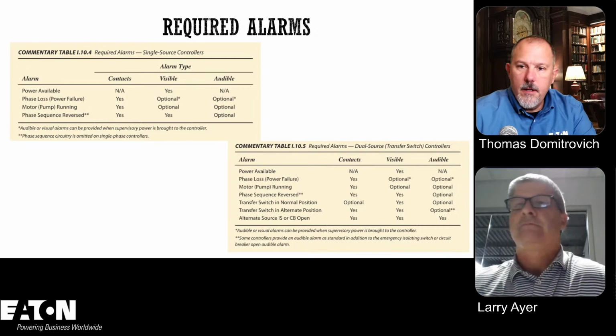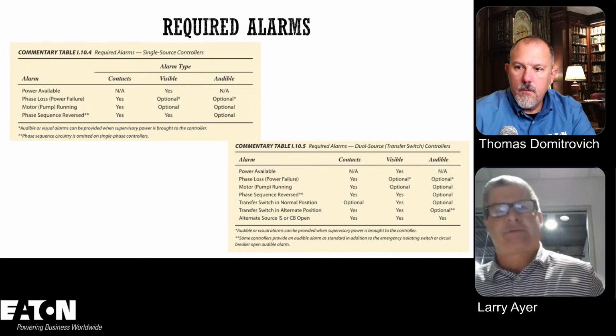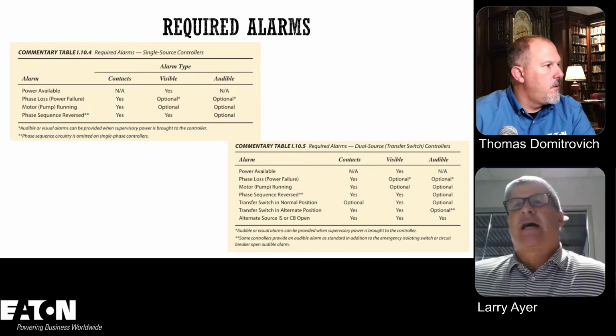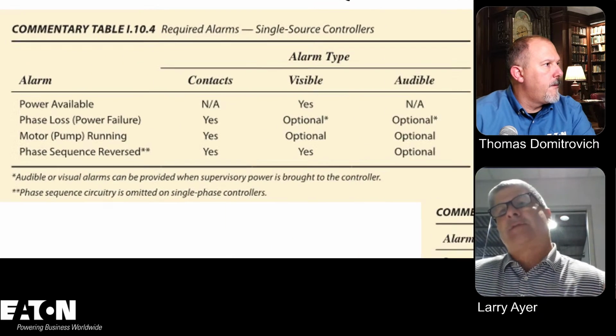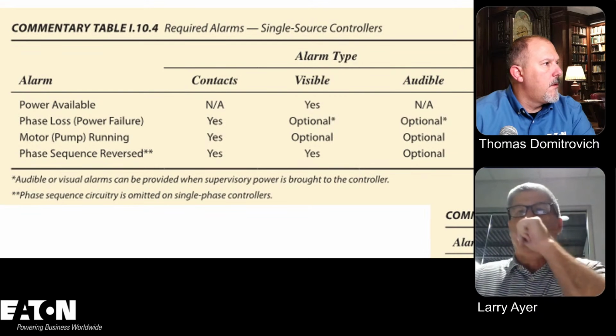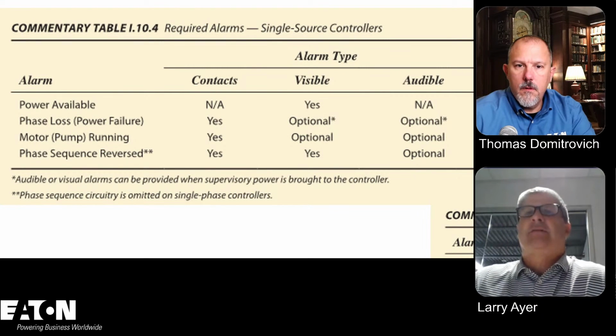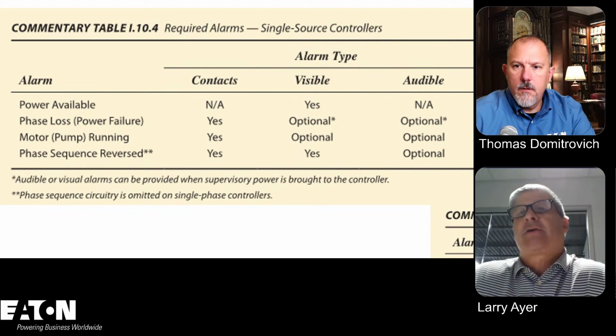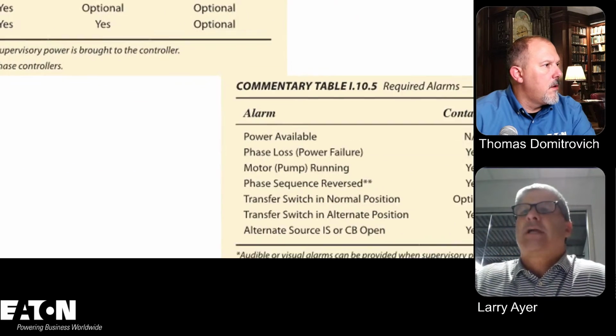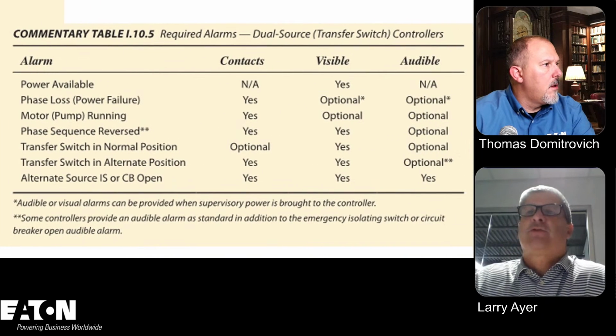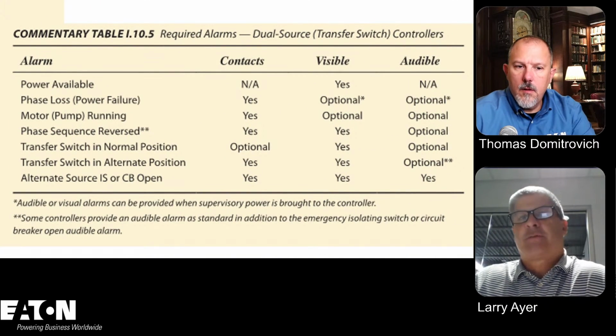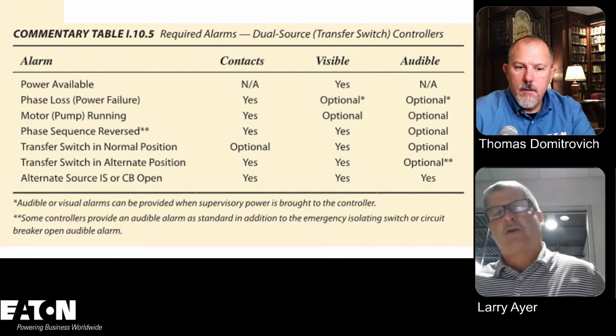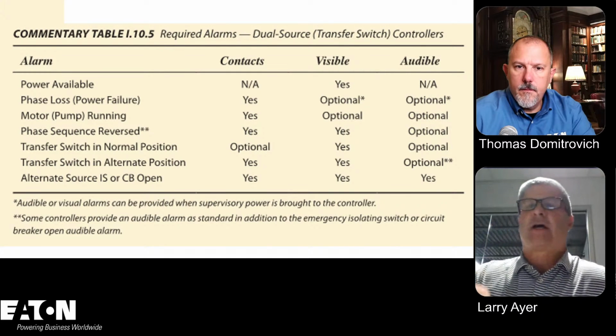Okay. All right. And so if you look, there's 2 tables there. One of the tables at the top is if you have a single source controller, and the one at the bottom is saying, okay, if I have dual sources. So if you look at that there, I need to have at least alarm type for power available and for phase sequence reversal. So those are the 2 main visible alarms, and there's some optional ones in there. And if you have dual sources, you need to have, for power available, phase sequence, transfer switch in normal or alternate position, or alternate source IS or circuit breaker open.